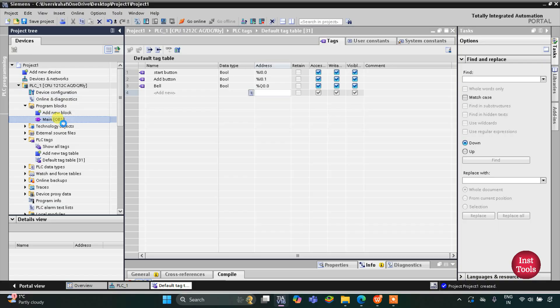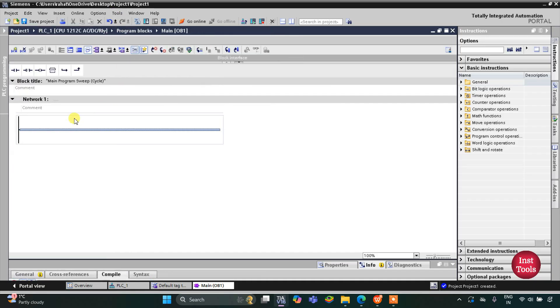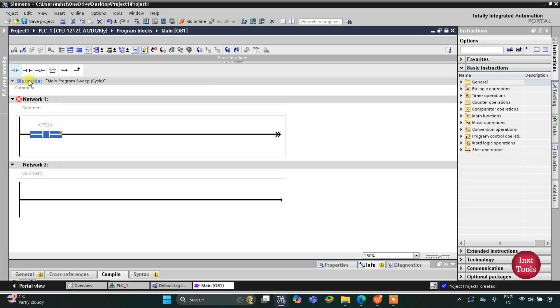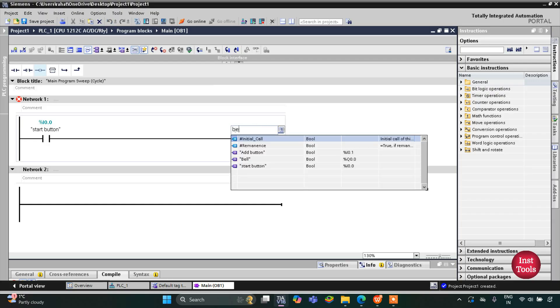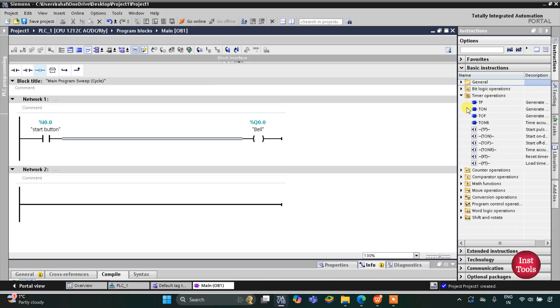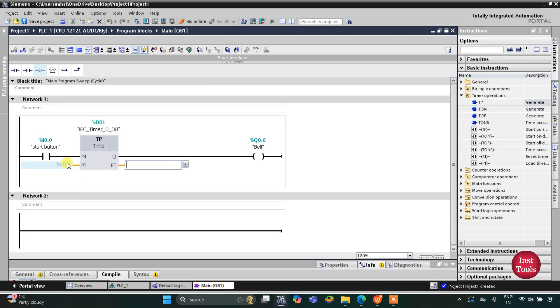After that I will go to Program Blocks and then Main OB1, where we will draw the ladder diagram. I will insert a normally open contact for the start button and a coil for the bell. When the start button is turned on, the bell gets on for 10 seconds. For that we will use a TP timer operation with a preset value of 10 seconds.